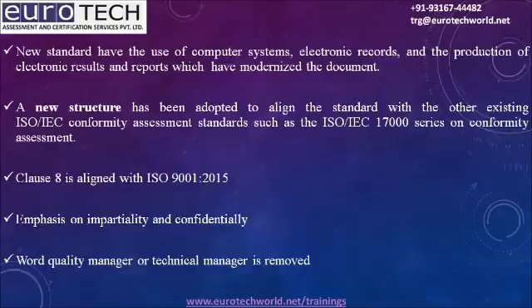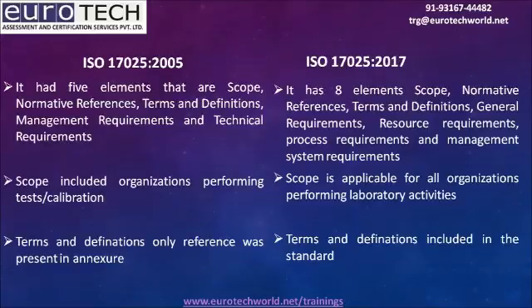A new structure has been adopted to align the standard with other existing ISO IEC conformity assessment standards, such as the ISO IEC 17000 series. Clause 8 is aligned with ISO 9001:2015. There is increased emphasis on impartiality and confidentiality. The roles of 'quality manager' or 'technical manager' have been removed from the standard.